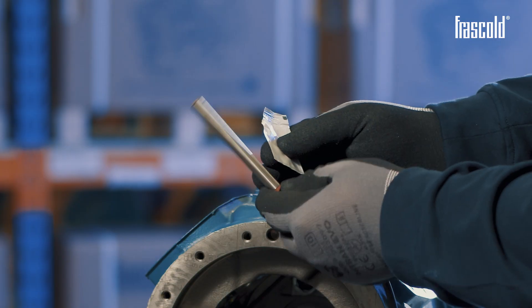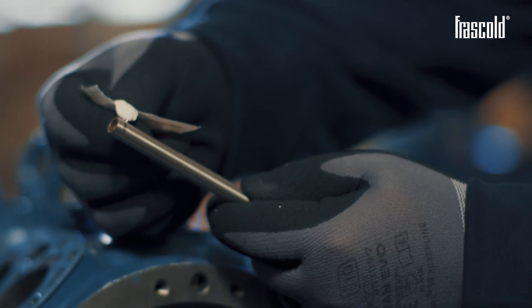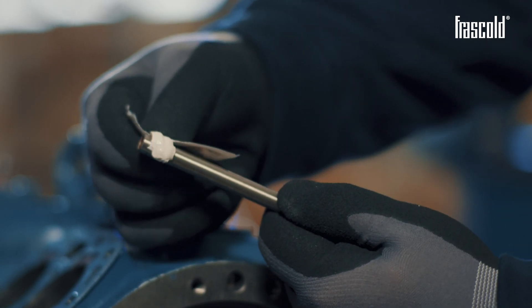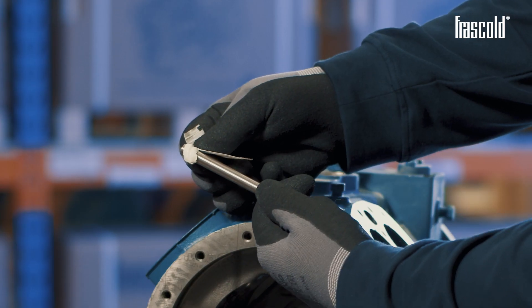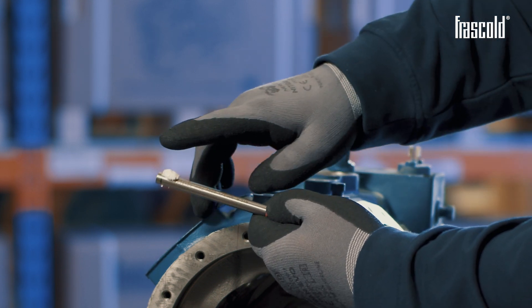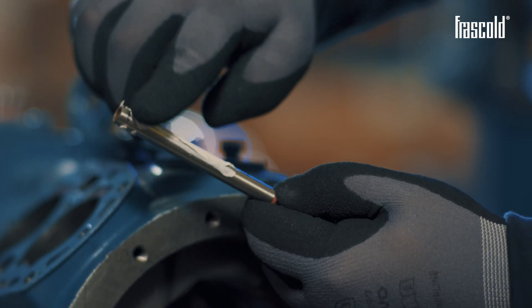How to avoid damage to the mechanics caused by excessive presence of the refrigerant gas? We recommend using a crankcase heater. This improvement, used after a period of compressor standstill, minimizes the presence of the liquid refrigerant in the oil sump, and thus ensures suitable lubrication which does not trigger seizures.